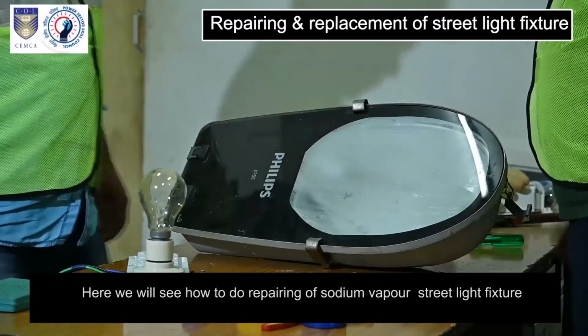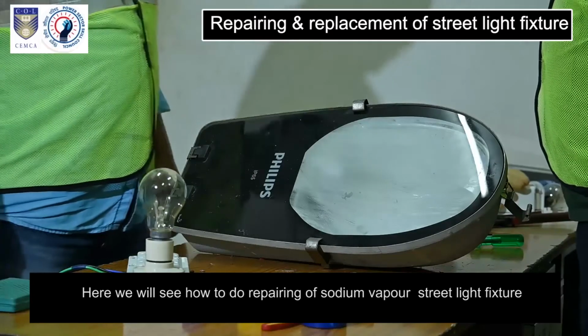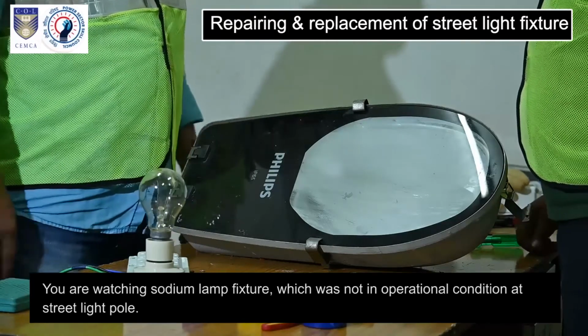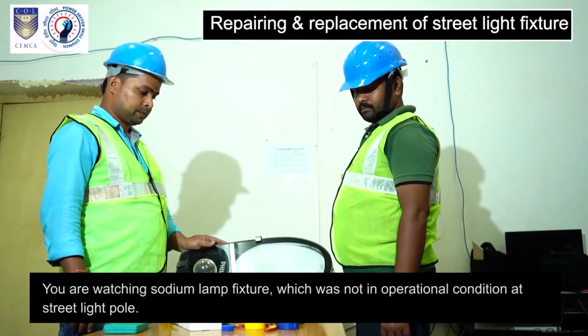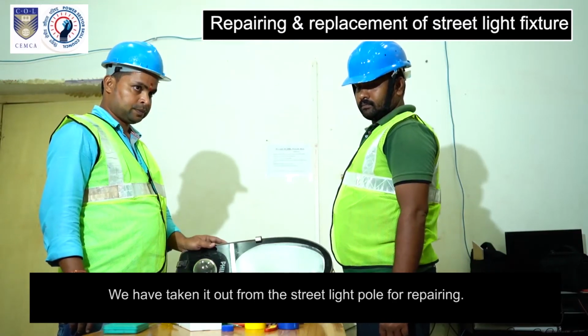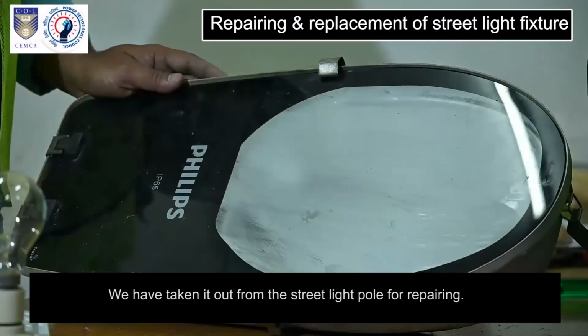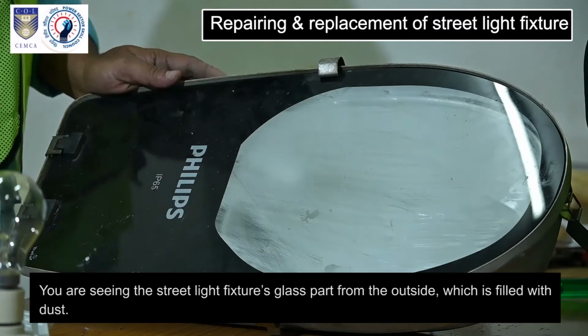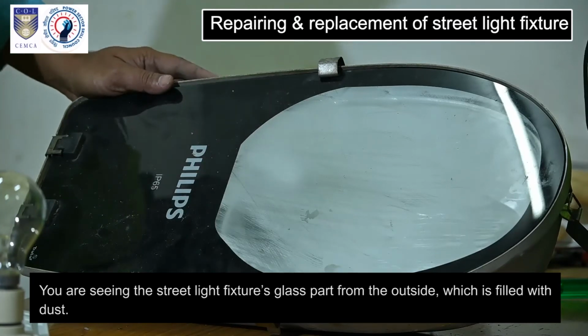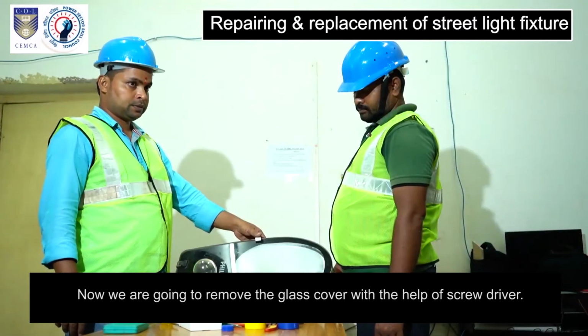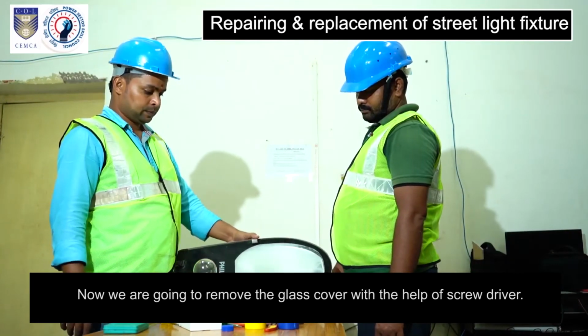Here we will see how to repair a sodium vapor street light fixture. You are watching a sodium lamp fixture, which was not in operational condition at the street light pole. We have taken it out from the street light pole for repairing. You are seeing the street light fixture's glass part from the outside, which is filled with dust. Now we are going to remove the glass cover with the help of a screwdriver.